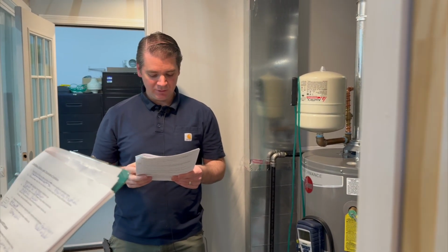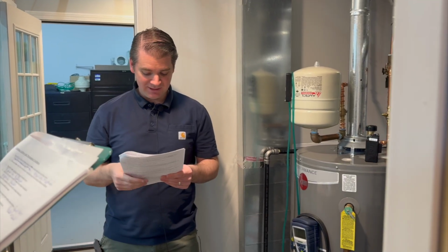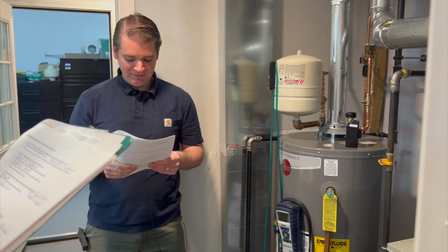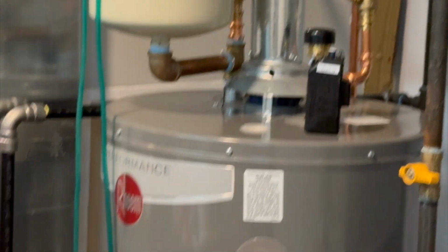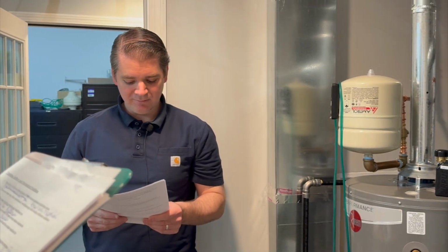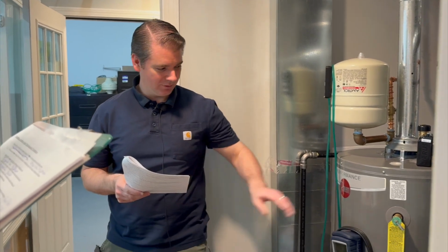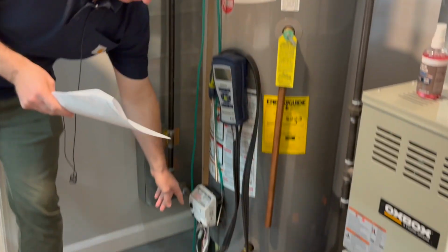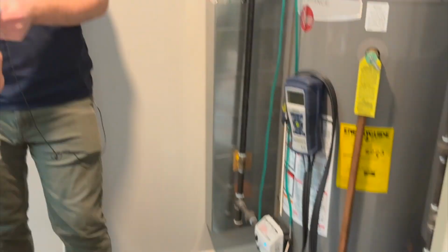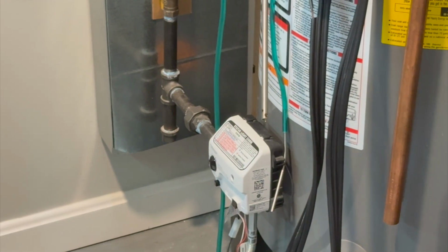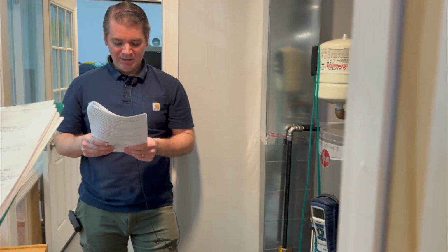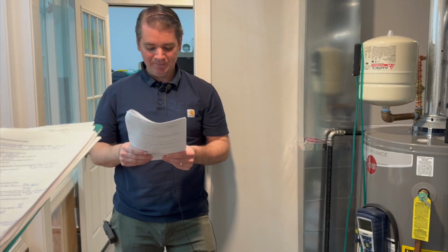For the domestic hot water heater, identify the fuel source, that's natural gas. Appliance type, it's a tank. Venting, natural draft, atmospherically vented. And heating capacity, 30,000 BTUs. Identify 2 basic components and controls. Well, one basic component would be the tank. The second would be the thermostat. Describe how to control the domestic hot water temperature settings. Well, with the thermostat, we can rotate it clockwise to make the water hotter, or turn it counterclockwise to lower the temperature.